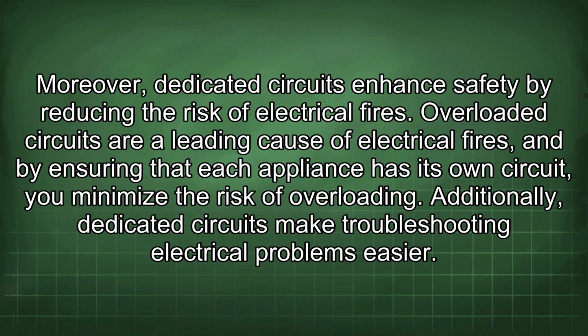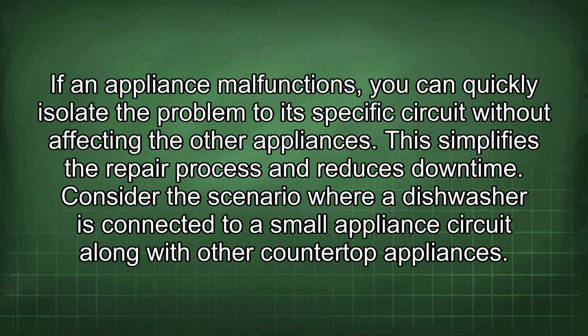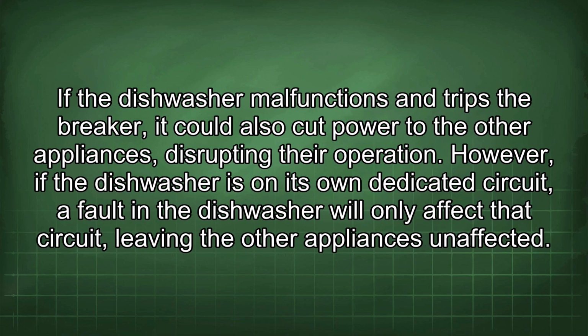Additionally, dedicated circuits make troubleshooting electrical problems easier. If an appliance malfunctions, you can quickly isolate the problem to its specific circuit without affecting the other appliances. This simplifies the repair process and reduces downtime. Consider the scenario where a dishwasher is connected to a small appliance circuit along with other countertop appliances. If the dishwasher malfunctions and trips the breaker, it could also cut power to the other appliances, disrupting their operation. However, if the dishwasher is on its own dedicated circuit, a fault in the dishwasher will only affect that circuit, leaving the other appliances unaffected.